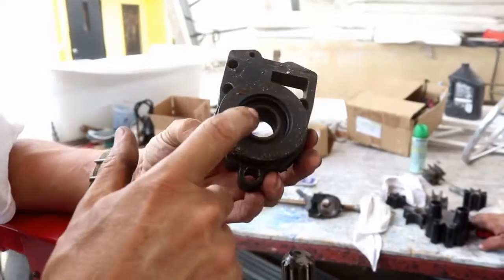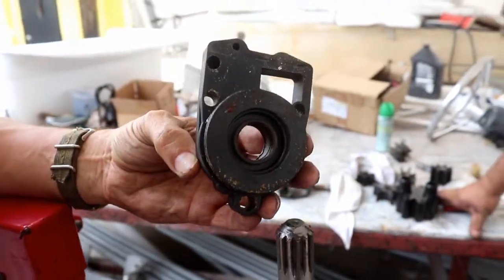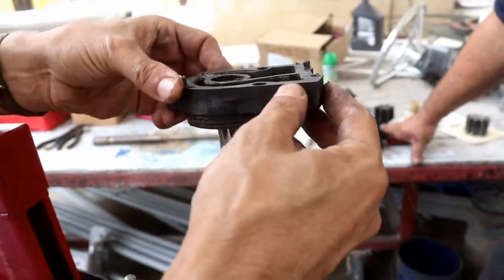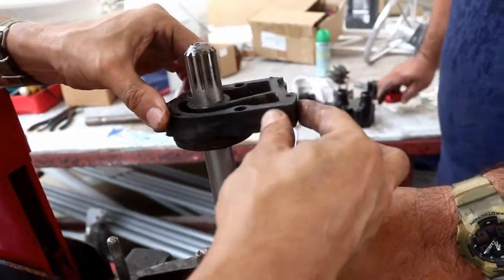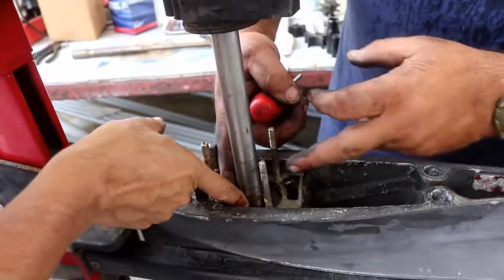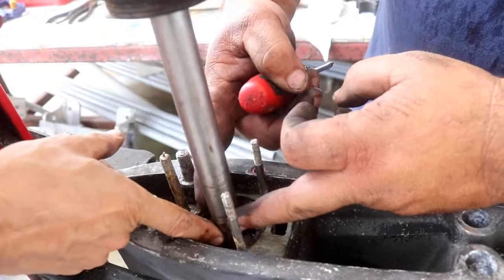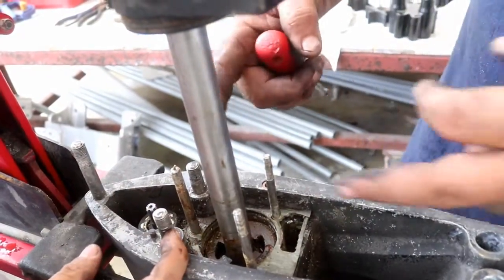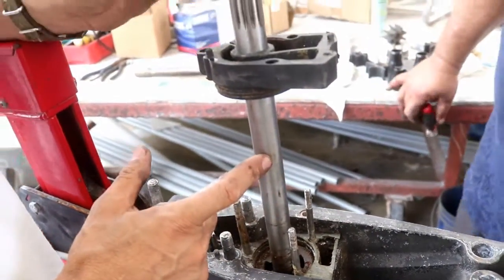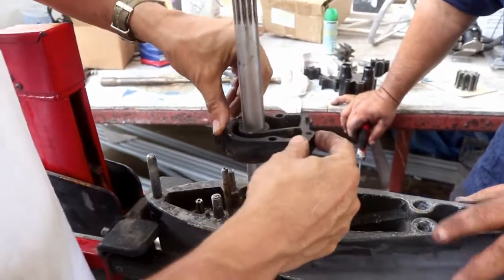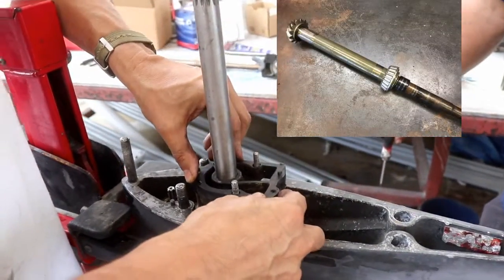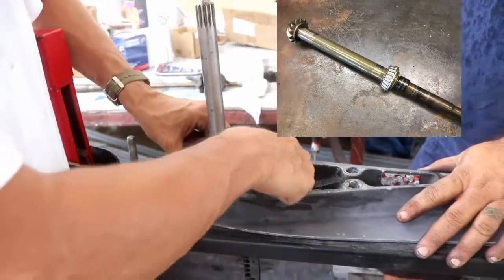To avoid damaging the seal, you put grease on the shaft and introduce it carefully, moving it in. You have to inspect the shaft, because sometimes the seal will cut a groove into it and it won't seal properly, so you may have to replace the shaft. I'll show you a picture of that on the screen.